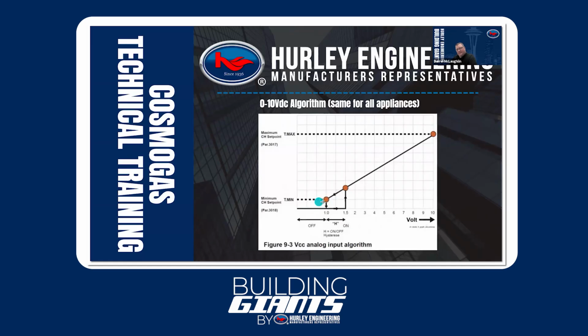By the same token, we can't tell it to turn back on at 1 because then if we're sitting real close to that, we might bounce back and forth and we might have some short cycling of the equipment. So the boiler won't turn back on until that signal is increased to 1.5 volts. But our minimum temperature is still determined. So you would increase the signal to 1.5, then you could drop it back to 1 volt to reach your minimum set point, if that's what you desired.